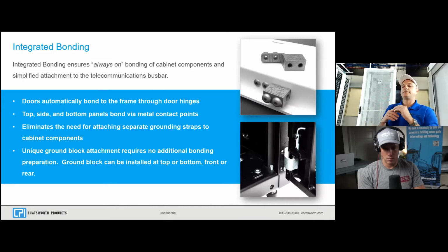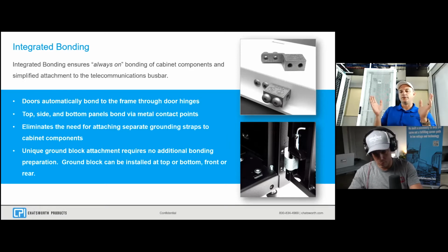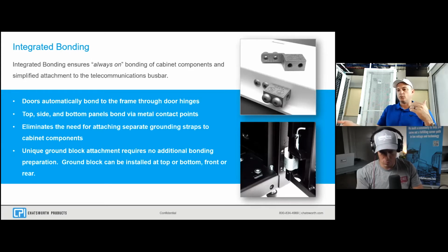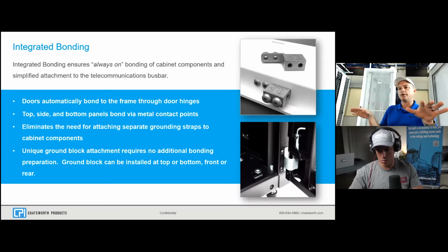Integrated bonding: we took an always-on approach to bonding with ZetaFrame. Traditionally, when you open the cabinet door, you're used to seeing these green wires that connect the door to the frame, or connect the side panels, top panel, and bottom panel to the frame. Any of these major subcomponents of a cabinet require this electrical bonding wire, and there's a safety element to that - it's a UL component. So what we did was figure out a way to eliminate those altogether.